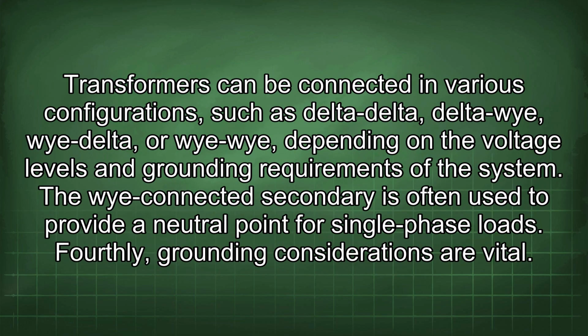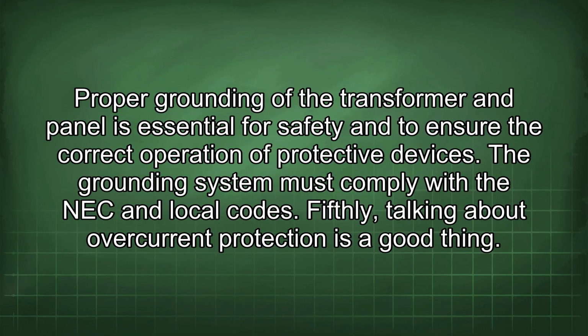Transformers can be connected in various configurations such as delta-delta, delta-Y, Y-delta, or Y-Y, depending on the voltage levels and grounding requirements of the system. The Y-connected secondary is often used to provide a neutral point for single-phase loads. Fourthly, grounding considerations are vital. Proper grounding of the transformer and panel is essential for safety and to ensure the correct operation of protective devices. The grounding system must comply with the NEC and local codes.